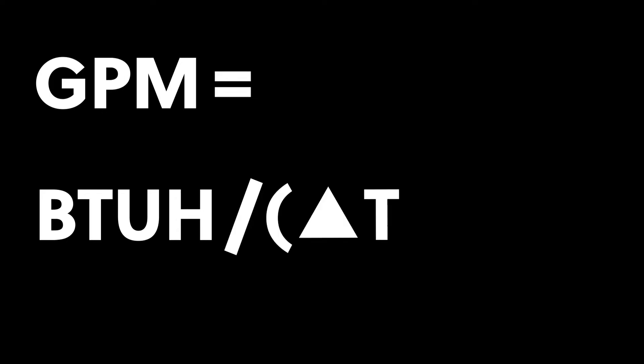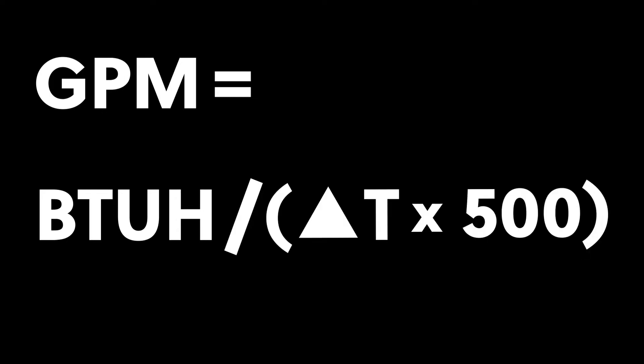So here's the formula. It's GPM equals BTUH divided by delta T times 500. Let's go over what each of those means.